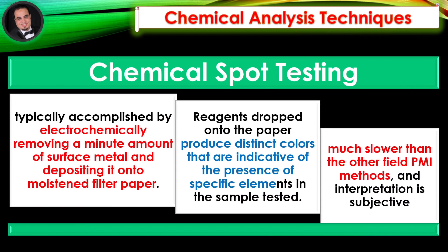Chemical Spot Testing. The chemical spot test is typically accomplished by electrochemically removing a minute amount of surface metal and depositing it onto moistened filter paper. Reagents dropped onto the paper produce distinct colors that are indicative of the presence of specific elements in the sample tested. Chemical spot testing is much slower than the other field PMI methods and interpretation is subjective.